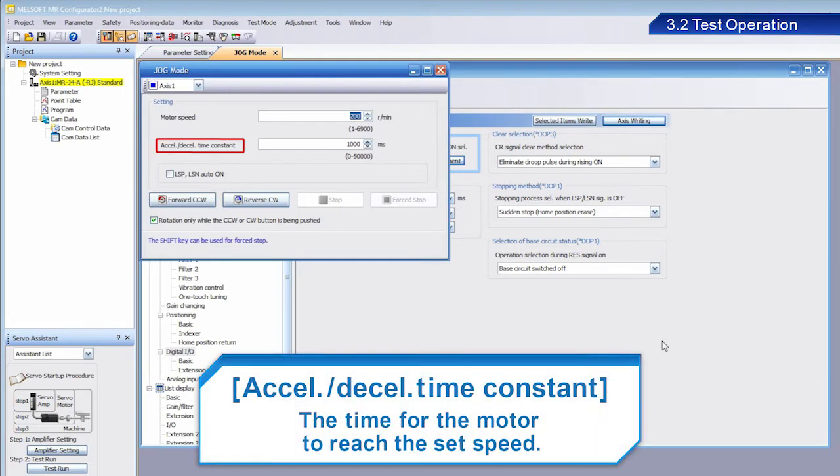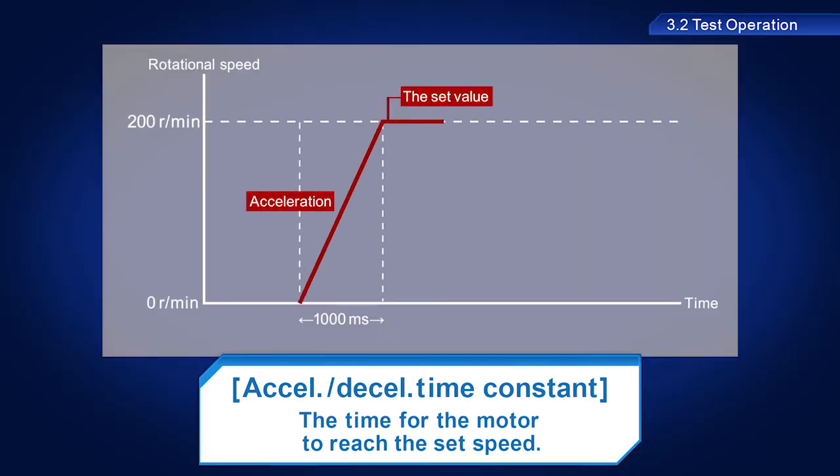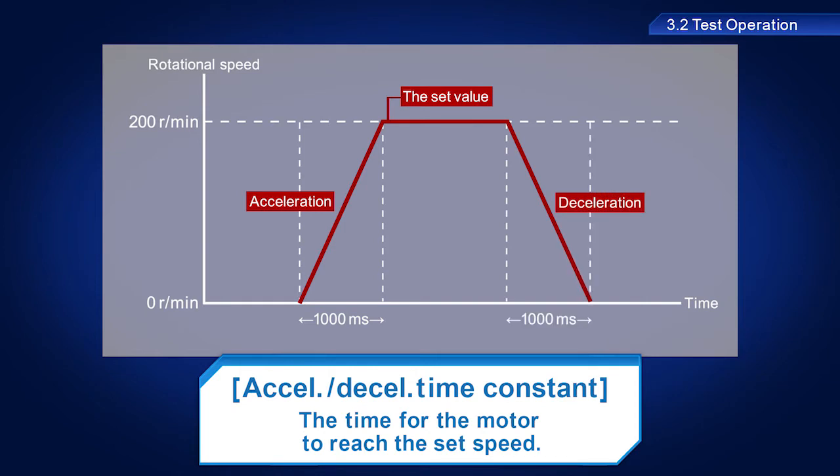Acceleration-deceleration time constant sets the time for the motor to reach the set speed. This is also the time used to decelerate the motor to a stop. For this training, we will set a value of 1000 milliseconds, so that it takes one second for the motor to reach the set speed of 200 revolutions per minute after starting.